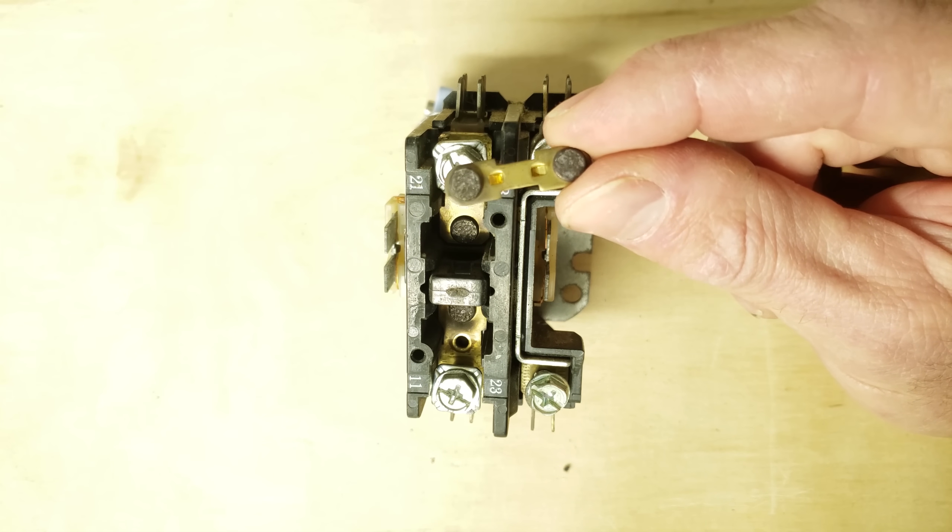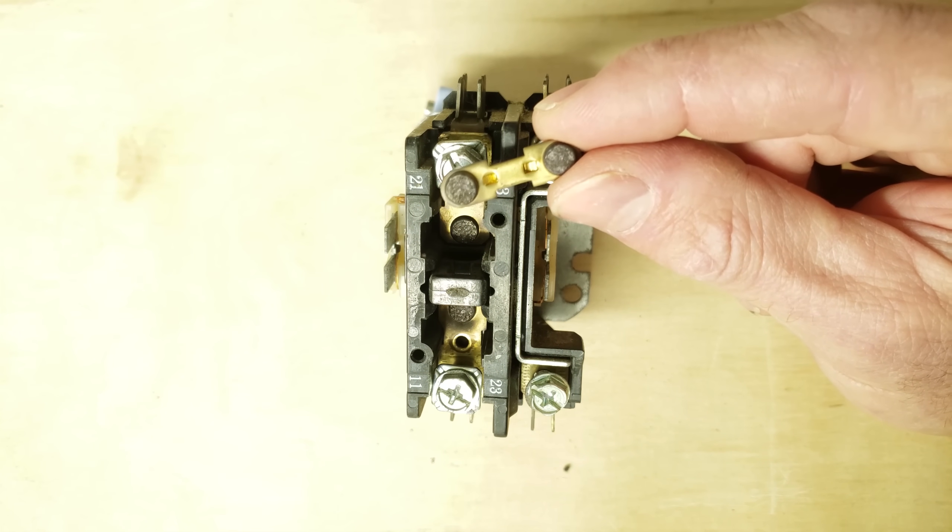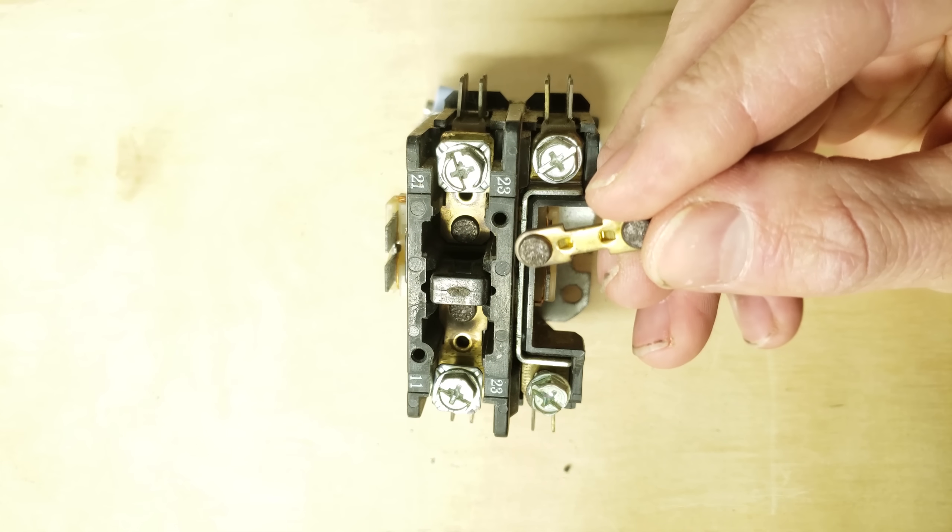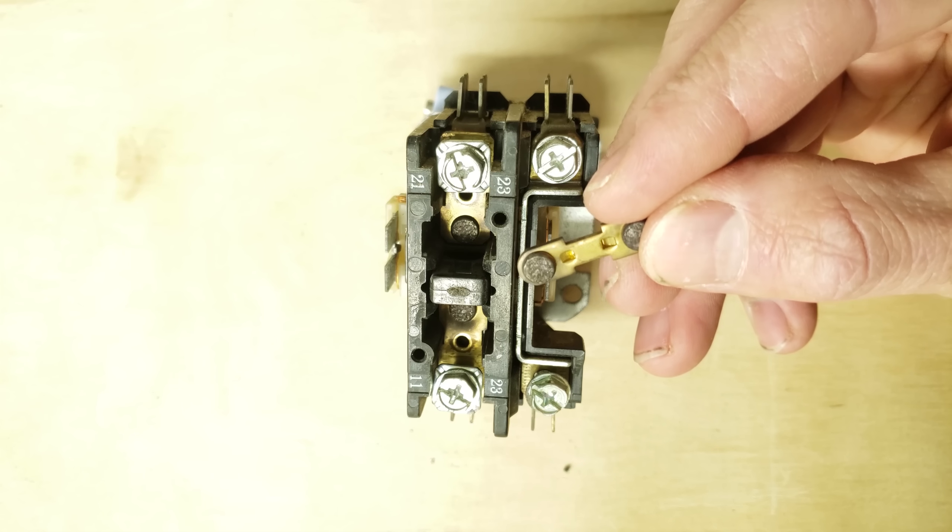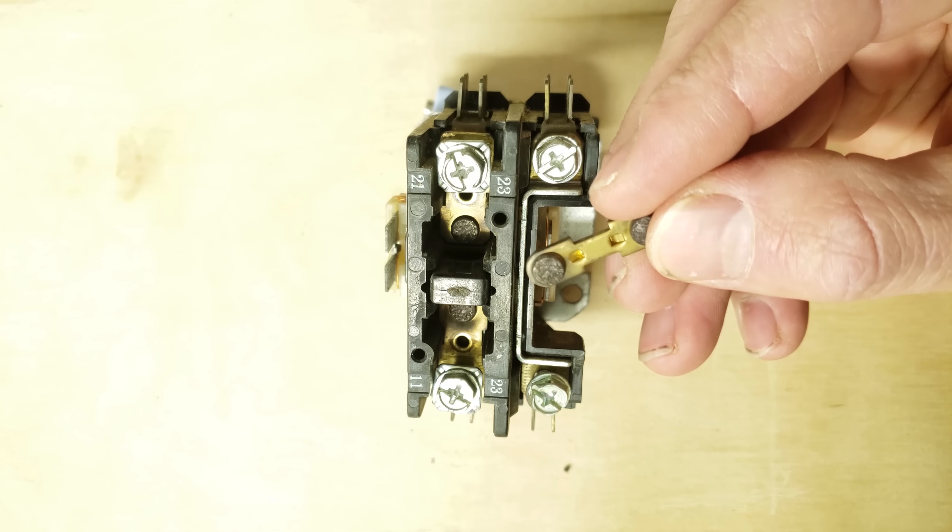Here's a look at some burnt contacts. You can see when these are actually touching this would go in here like this. But when these touch you have a high resistance reading and that's just because you have a buildup on the actual contacts themselves.